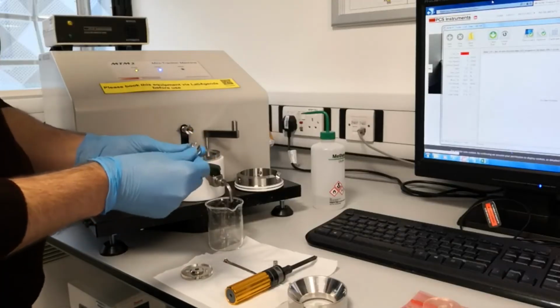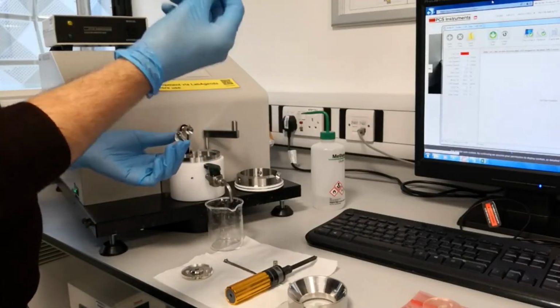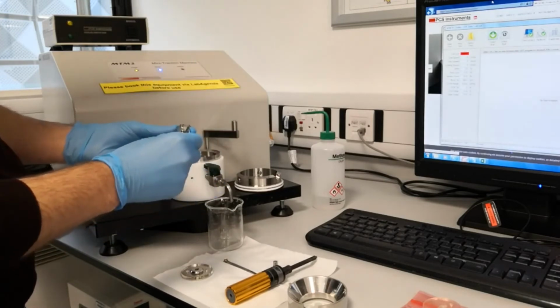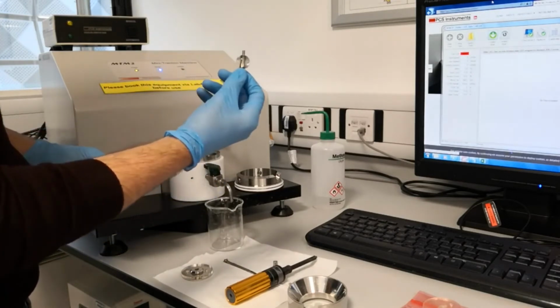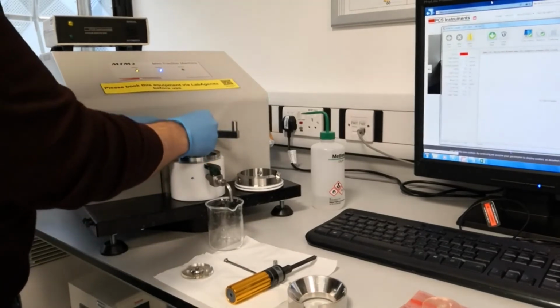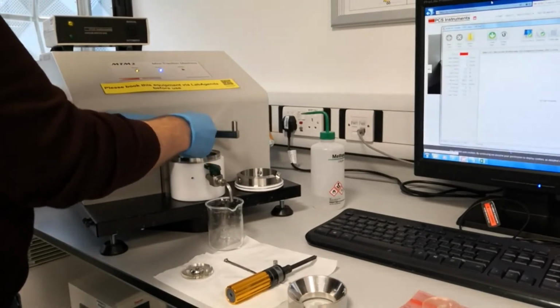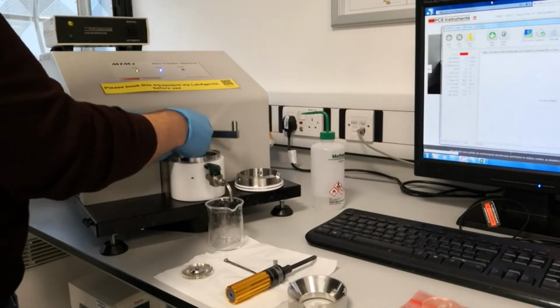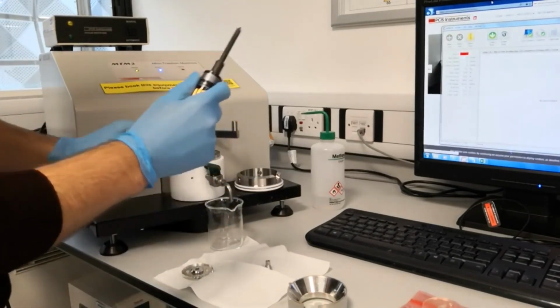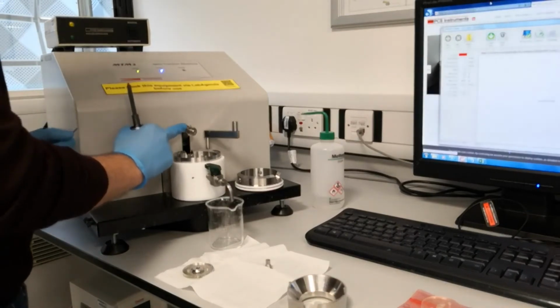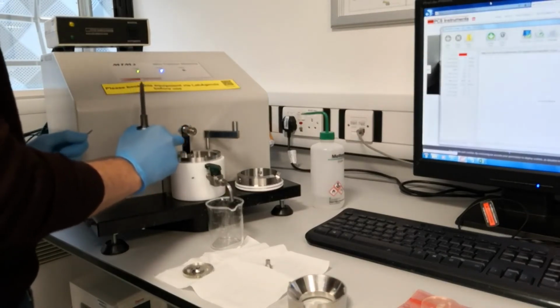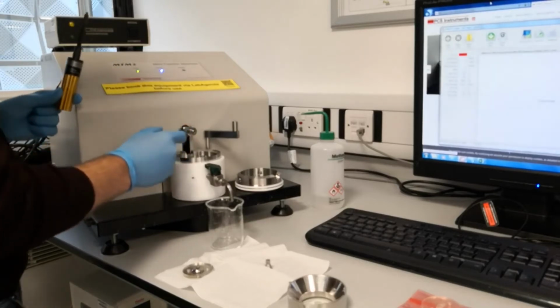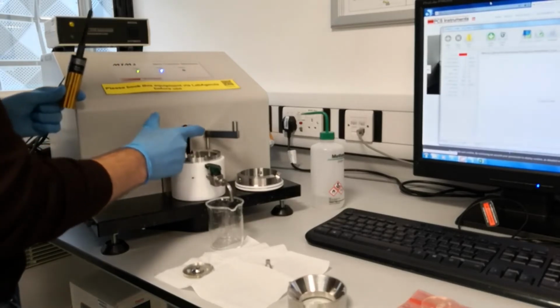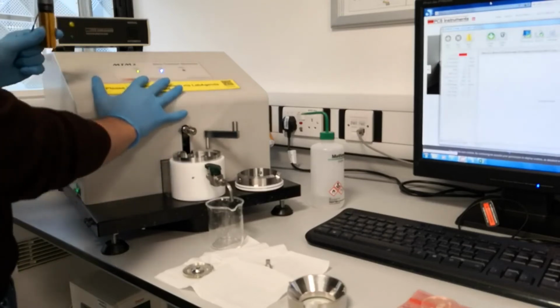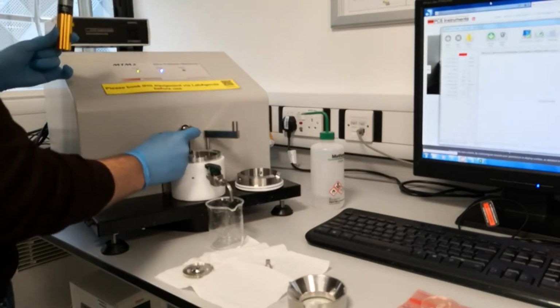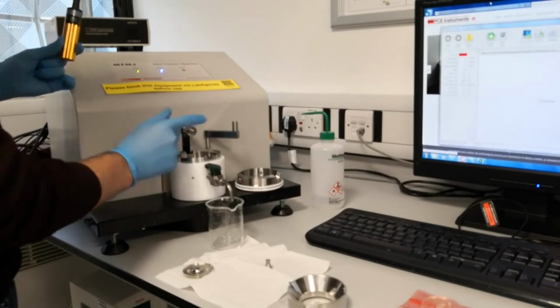Okay, so how do you mount your samples into the machine? You need this screw, which is a retaining screw for the ball, and it goes through the ball and into the shaft, and you tighten your ball into the shaft using two screwdrivers. This shaft is applying the load and also measuring the friction. So when you have tangential forces, the torque transducer sitting inside this box would measure the friction on the left or right hand side.